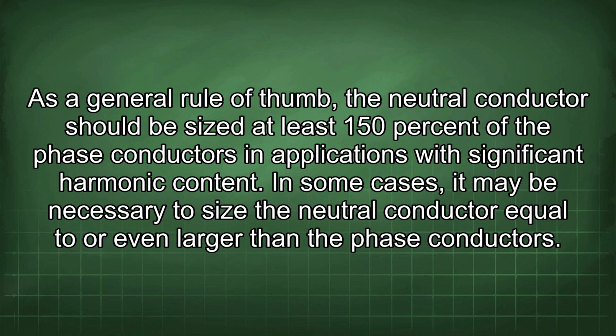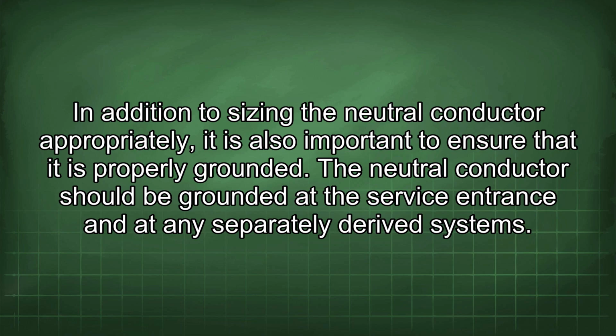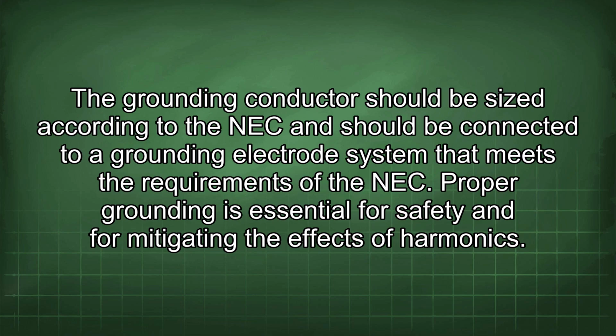As a general rule of thumb, the neutral conductor should be sized at least 150% of the phase conductors in applications with significant harmonic content. In some cases, it may be necessary to size the neutral conductor equal to or even larger than the phase conductors. In addition to sizing the neutral conductor appropriately, it is also important to ensure that it is properly grounded. The neutral conductor should be grounded at the service entrance and at any separately derived systems. The grounding conductor should be sized according to the NEC and should be connected to a grounding electrode system that meets the requirements of the NEC.